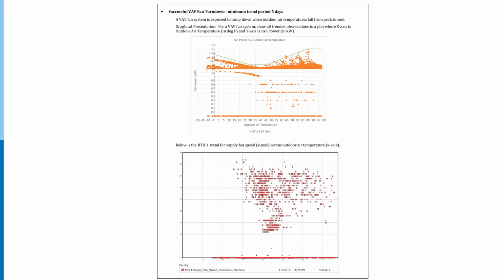You can kind of see this slight dip in the data between 40 and 50 degrees, but other than that, it really doesn't bear any real resemblance to the chart above. And it's pretty broad, right? Those fans are ramping up and down between 25 and 40%. They track speed here rather than fan power, but that's okay.